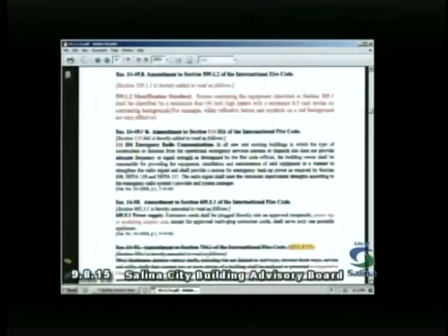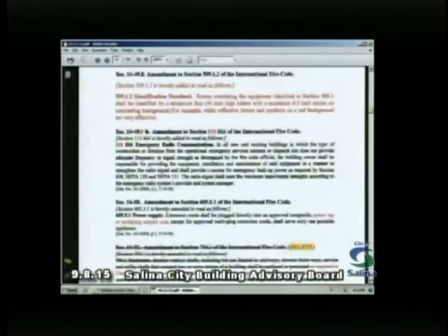We now have an identification standard. If we look at 509.1.2, the rooms containing the equipment, and we're talking about your fire sprinkler riser rooms, those type things, they're now required to be identified with a minimum of 4-inch high letters, a minimum 1/2 inch stroke on a contrasting background to identify those rooms, whether it's fire sprinkler room, fire alarm panel, whatever the case may be.